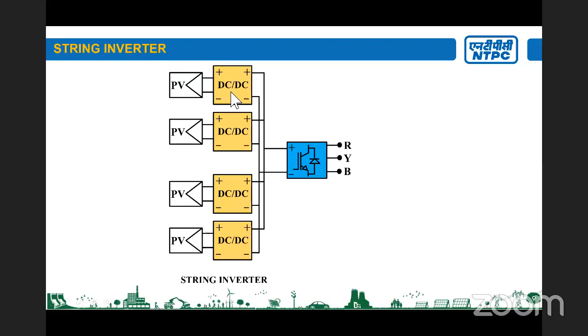So this is the control of the central inverter. It is required to control the PV side, like maximum power point tracking, and on the grid side, it is required to control active power and reactive power. Then there are different grid compliance requirements like HVRT, LVRT, frequency response, and anti-islanding. And at the top, I mentioned the MPPT range.